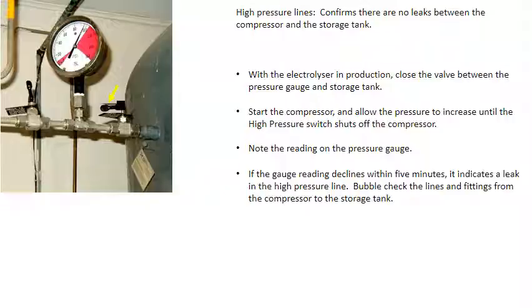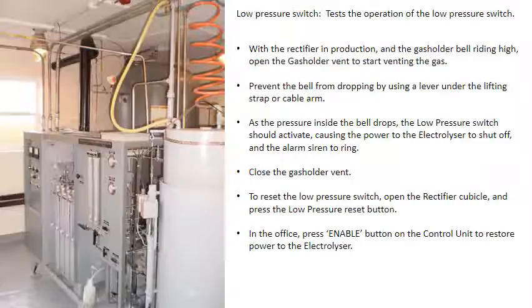The high pressure test confirms there are no leaks between the compressor and the storage tank. With the electrolyzer in production, close the valve between the pressure gauge and the storage tank. Start the compressor and allow the pressure to increase until the high pressure switch shuts off the compressor. Note the reading on the pressure gauge. If the gauge reading declines within 5 minutes, it indicates a leak in the high pressure line. Bubble check the lines and fittings from the compressor to the storage tank.